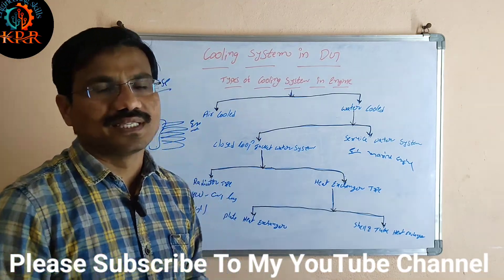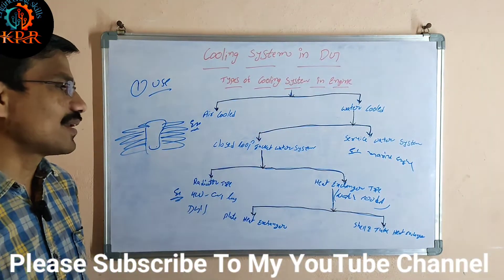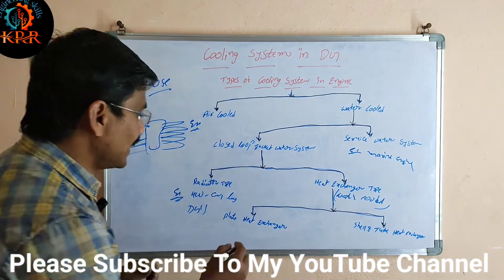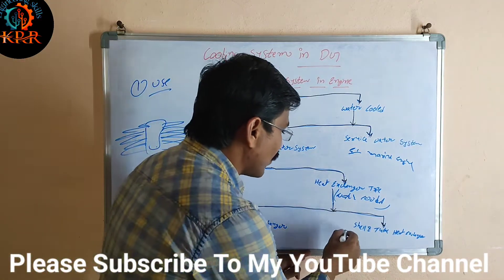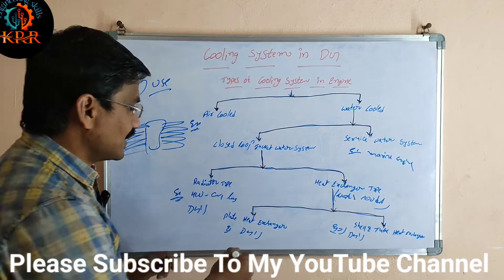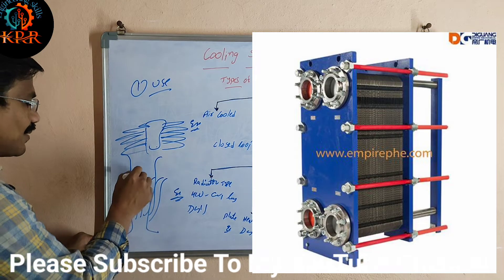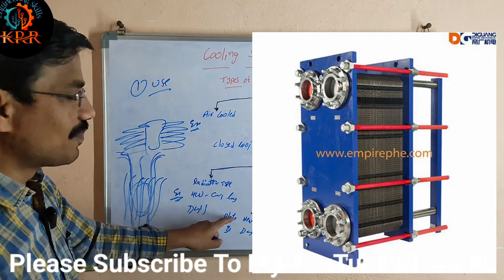The second type is the heat exchanger water-cooled system. The heat exchanger water-cooled system may be classified into two types: one is the plate heat exchanger and the second is the shell and tube heat exchanger. These two are mainly used for diesel generators. For heavy-rating diesel generators, we use the plate heat exchanger, and for small-rating diesel generators, we use the shell and tube heat exchanger. In the plate heat exchanger, some plates are there — water is coming and going through some plates, and coolant is coming and going through other plates. With the help of this water, the coolant gets cooled. That is called the plate heat exchanger type coolant system.